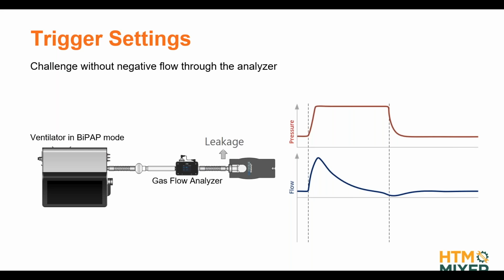And if you look at the different pressure and flow waveforms for this example, you see the flow waveform is not really sufficient for triggering due to the lack of a steep falling or rising edge. On the other hand, we see that our pressure signal is actually pretty good, right? So in such a situation, we would typically use the pressure signal to trigger.